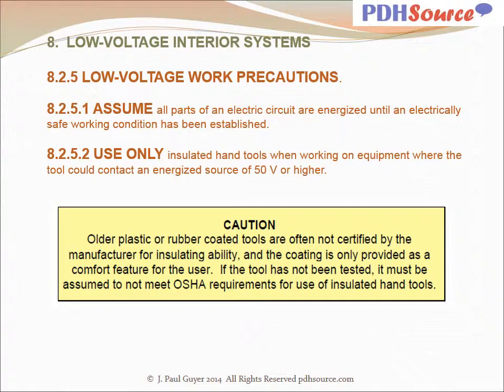Assume all parts of an electric circuit are energized until an electrically safe working condition has been established. Use only insulated hand tools when working on equipment where the tool could contact an energized source of 50 volts or higher. Caution: older plastic or rubber-coated tools are often not certified by the manufacturer for insulating ability, and the coating is only provided as a comfort feature for the user. If the tool has not been tested, it must be assumed to not meet OSHA requirements for use of insulated hand tools.